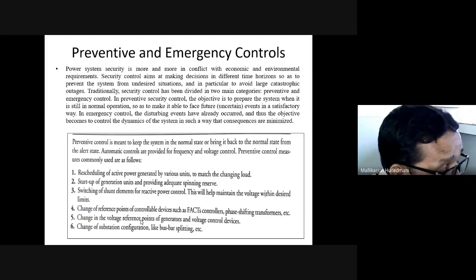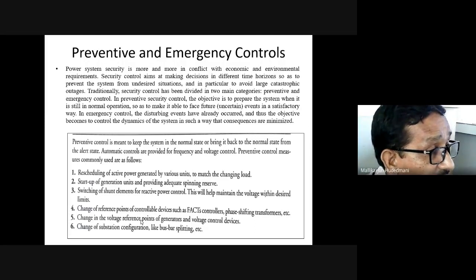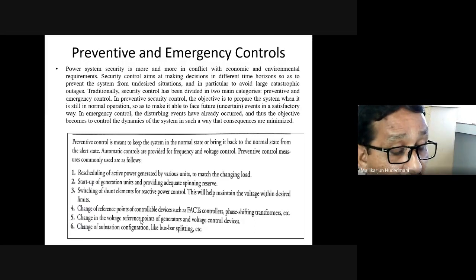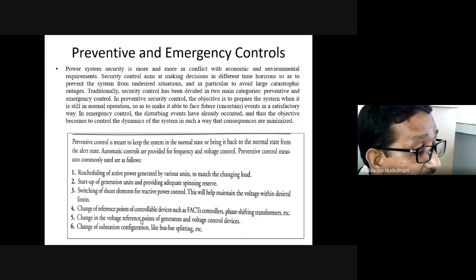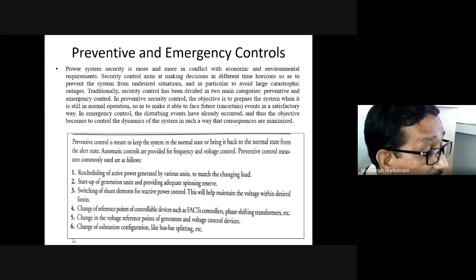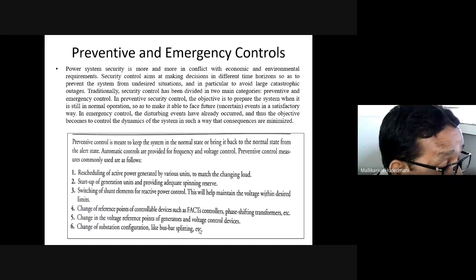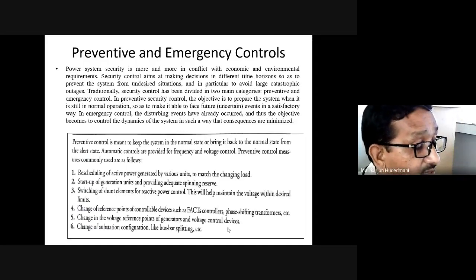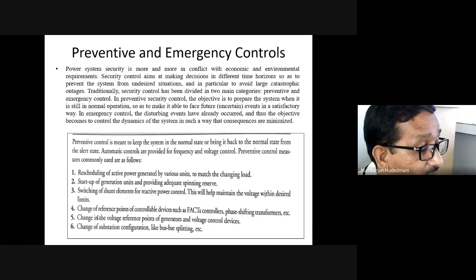The reference point, when I said a certain generator is 11 kV, is generating 11 kV. We are generating 11.6, 11.4 like that kV initially at the generating point. When it is generated and connected to a transformer and pumping it to the grid, it will definitely be reduced. In that due regard, where there is a facility, flexibility, freedom of change in set point should be adopted before really it is demanded by the requirement. That's how the flexibility we have needs to be encashed.